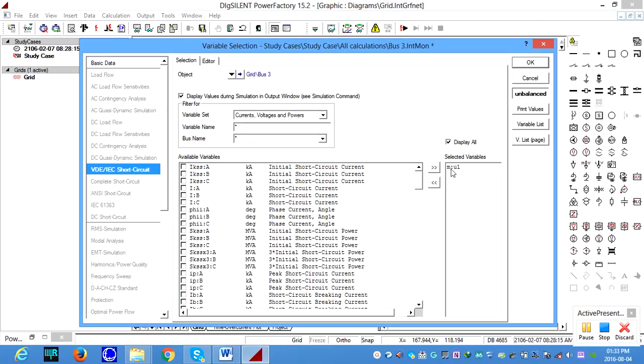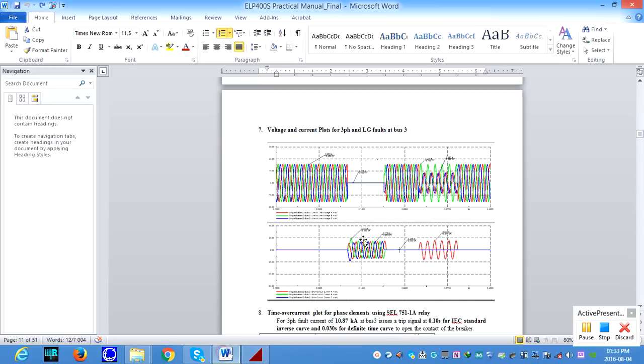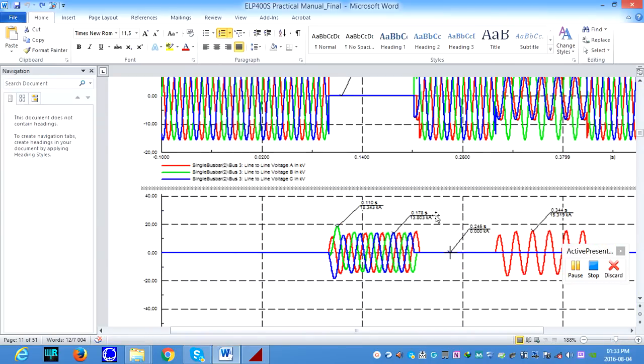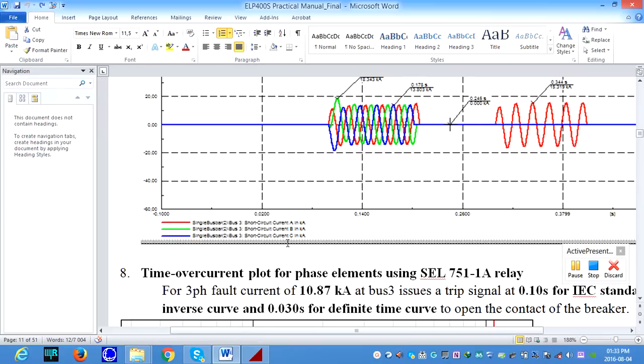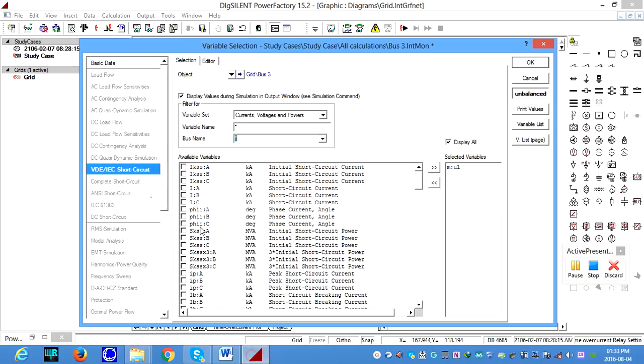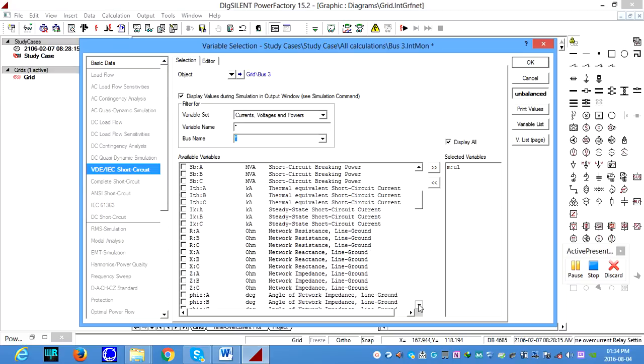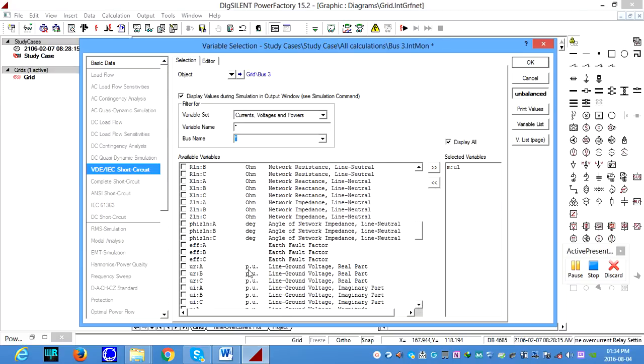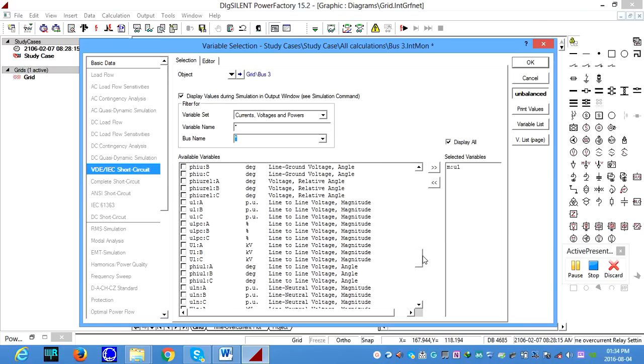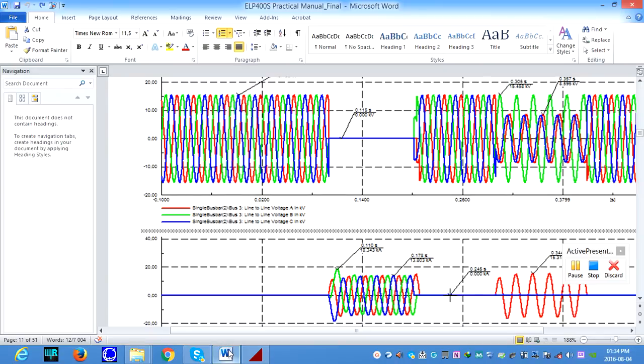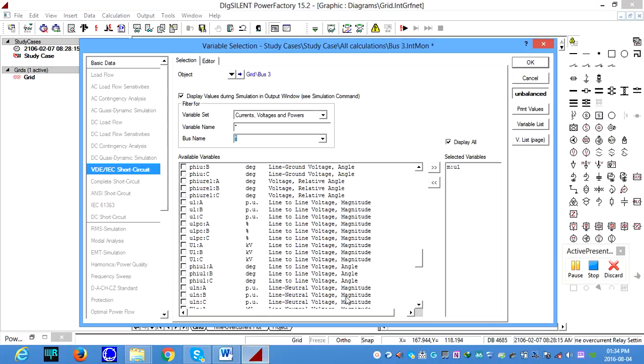Now we need to select, if you look at your graph, what elements will be there. Okay to zoom in. We're looking at your line to line voltages, phase A, phase B, phase C, and your short circuit current ABC at bus 3. So the line to line voltages, phase A, phase B, phase C, you can find down there. You can scroll down, and also make sure that it is in kilovolt or per unit. It is kilovolt, so you can go line to line voltages.